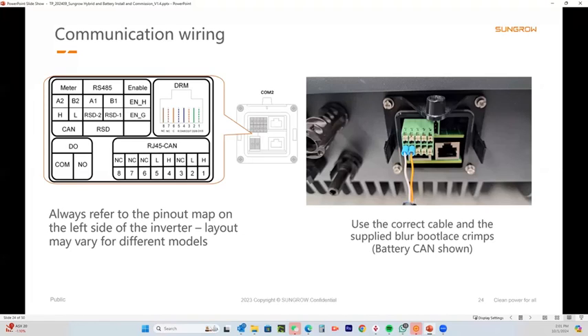Inverters didn't used to have all this on them, but now they do, so you do need to learn and know what you're doing with the communications. On the left hand side of every one of our inverters will have a pinout diagram, and it tells you where to connect everything. For what we do, there's only two of the terminals that we use. The meter A2, B2, which connects the energy meter, and the CAN is for the battery, CAN high, CAN low. These are the only ones that we use.